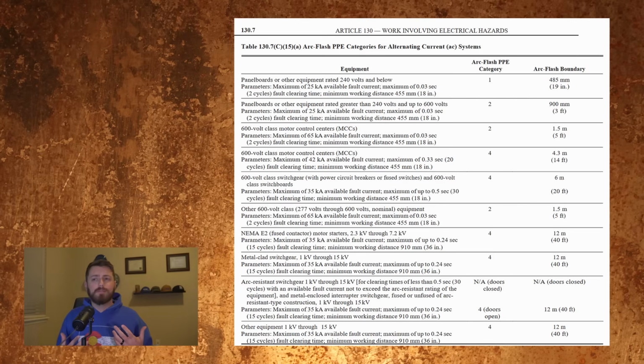Now, these tables make a lot of assumptions based off of the general ampacity and size of these types of equipment. But one assumption that varies substantially between switchgear, MCCs, switchboards, and panelboards is what we call the working distance. That's the distance between your greasy, flammable face and the energized bus. To assume the worst case scenario, for most of these, table 130.7 gives you two options for working distance. So 18 inches, which is roughly arm's length for the average size guy, and 36 inches, where there's a whole large breaker between you and the bus.